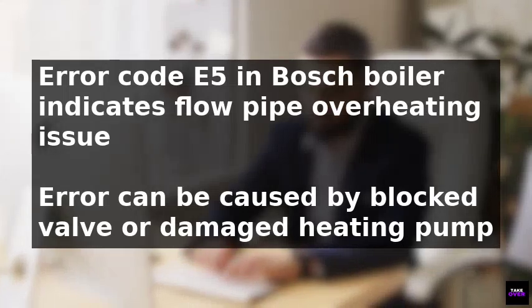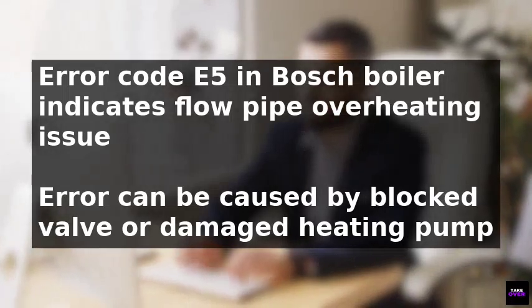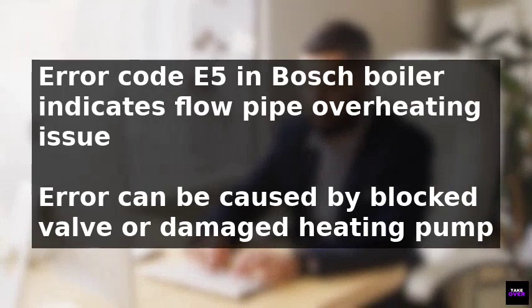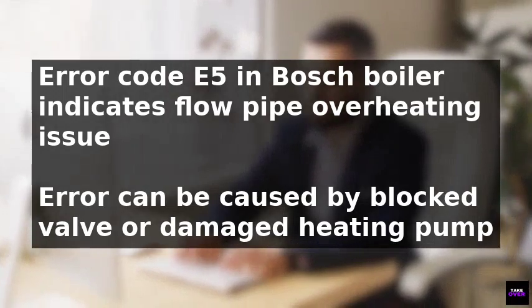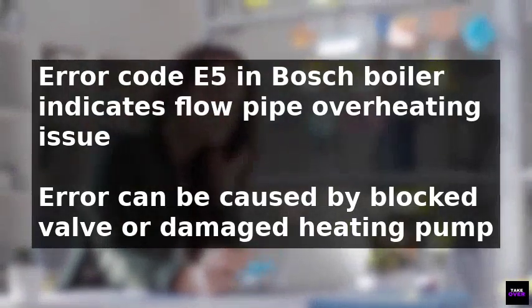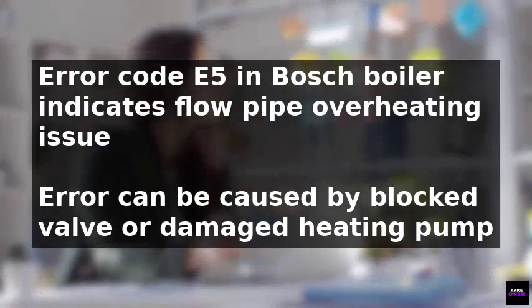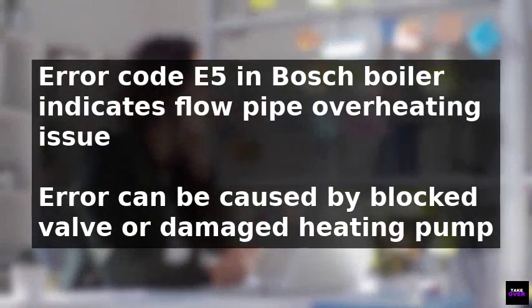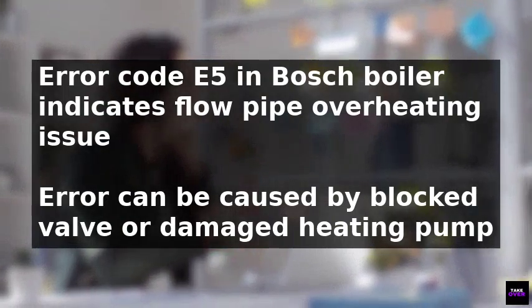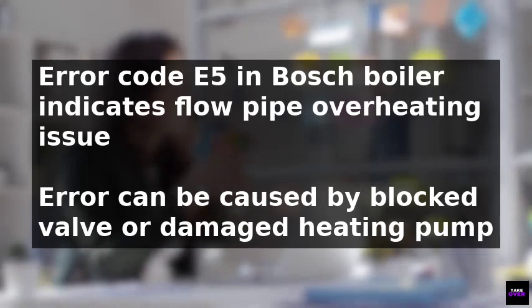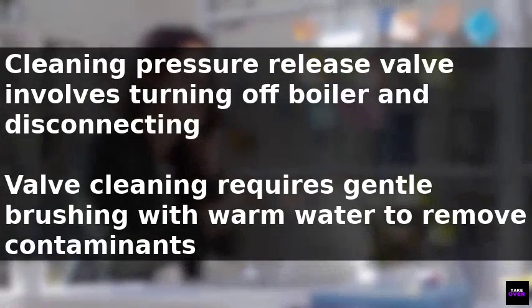The error code E5 in a Bosch boiler indicates that the flow pipe is overheating. This issue can be caused by several factors, including a blocked pressure release valve, a damaged heating pump, or a faulty thermistor. To fix the error, start by cleaning the pressure release valve.